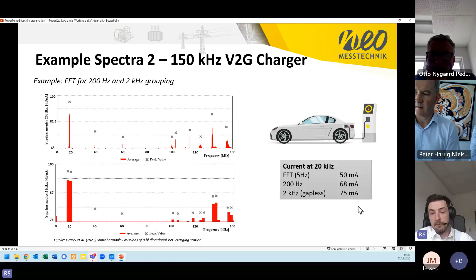You might think, this is just a few milliamps, what can be problematic here? But think also about the effects of supraharmonics - they can be spread somewhere in the grid, or quite locally. And with your LED light bulb - as we mentioned already before, the nominal current of an LED bulb is quite lower than this. And if you get this additional current, which can actually happen, you see that this will really damage your electrical equipment.